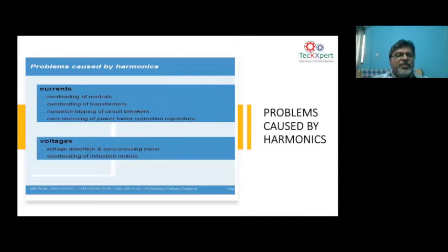And now to sum up harmonics, what all harmonics can cause: it can cause neutral overloading. As I told you, third harmonic current can always flow through the neutral because it is a zero sequence current. In a balanced network, you will not have negative and positive sequence currents. When an unbalance comes, and harmonics certainly cause an unbalance, then you have positive, negative, and zero sequence currents. The zero sequence currents rotate in line with the positive sequence current. So that means it comes to the neutral and flows through the neutral. That is why the neutral is getting overheated.